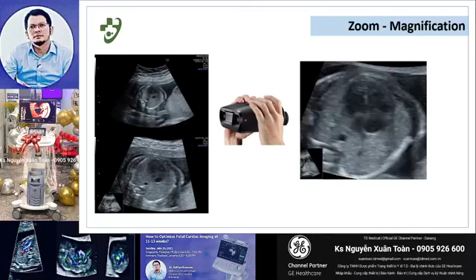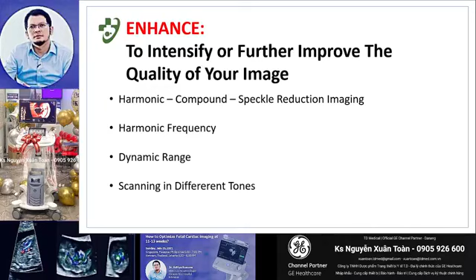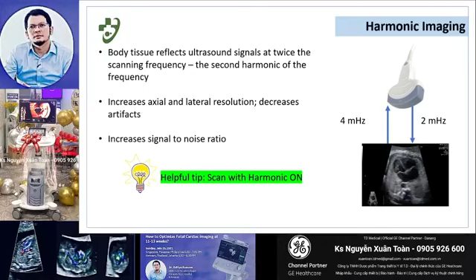And then how to enhance, to intensify or improve the quality. We need to be more detailed in harmonic frequency, dynamic range, and differences in tones. For harmonic imaging, body tissue reflects signals at twice the scanning frequency. It increases axial and lateral resolution and decreases artifact. So a helpful tip when we use our machine: we should put the harmonic on.